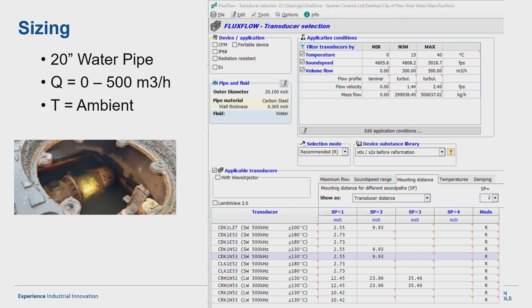But yeah, so they call that a 2-path. And what that number underneath tells us is how far apart the transducer should be mounted. So this is why the sizing is really important, because that tells us exactly where we should be mounting the transducers. And we don't want to just throw it on there willy-nilly. And if we get time, if I stop talking, then I'll show you what I mean by that.